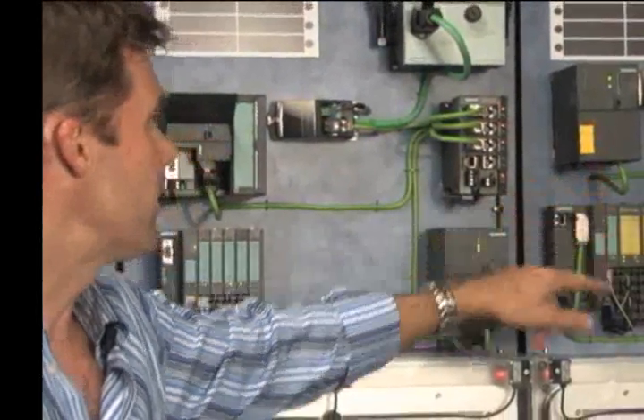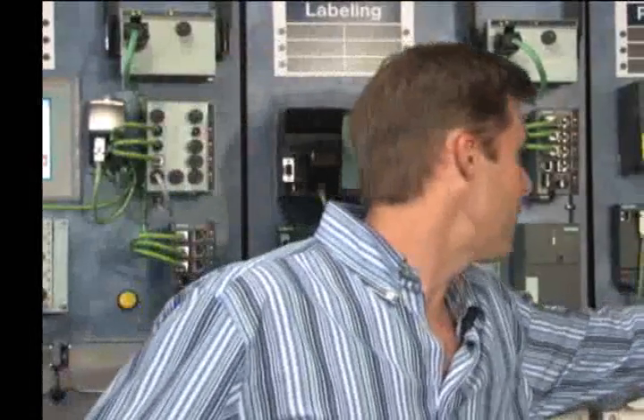So what this means is that it's certified to work with safety circuits, similar to the e-stop function you see here. And what this does is it eliminates an entire hardwired relay cabinet for the e-stop functionality, which we normally would have to have.